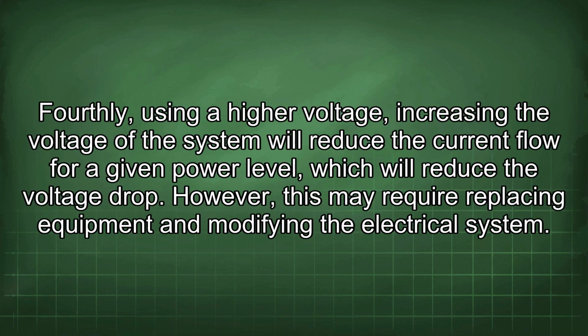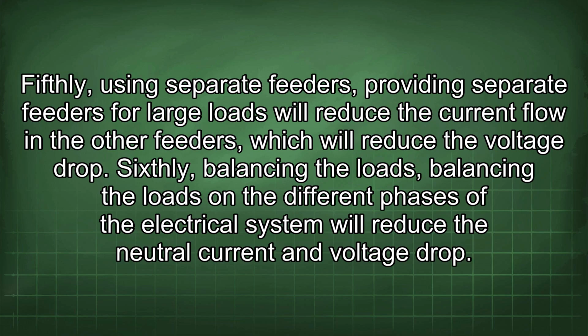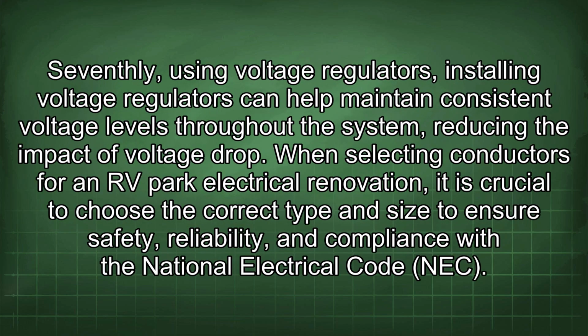Fourthly, using a higher voltage. Increasing the voltage of the system will reduce the current flow for a given power level, which will reduce the voltage drop. However, this may require replacing equipment and modifying the electrical system. Fifthly, using separate feeders. Providing separate feeders for large loads will reduce the current flow in the other feeders, which will reduce the voltage drop. Sixthly, balancing the loads. Balancing the loads on the different phases of the electrical system will reduce the neutral current and voltage drop. Seventhly, using voltage regulators. Installing voltage regulators can help maintain consistent voltage levels throughout the system, reducing the impact of voltage drop.